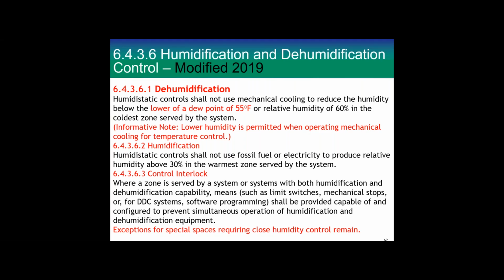Some exceptions. Humidification: humidistat control shall not use fossil fuel or electricity to produce relative humidity above 30% in the warmest zone served by the system. This is saying fossil fuel or electricity, and it's leading you to use an adiabatic type system, a spray type or something that does not use fossil fuel or electricity, if you need more than 30%. Control interlock: where a zone is served by a system or systems with both humidification and dehumidification capability, you have to interlock them so they don't fight each other, adding humidity at the same time you're removing it. There are some exceptions, of course, for museums and libraries and certain places, and there are some ways to set it up to get around it.